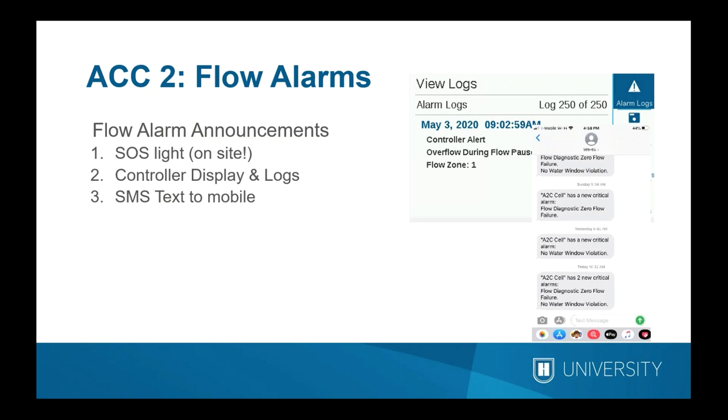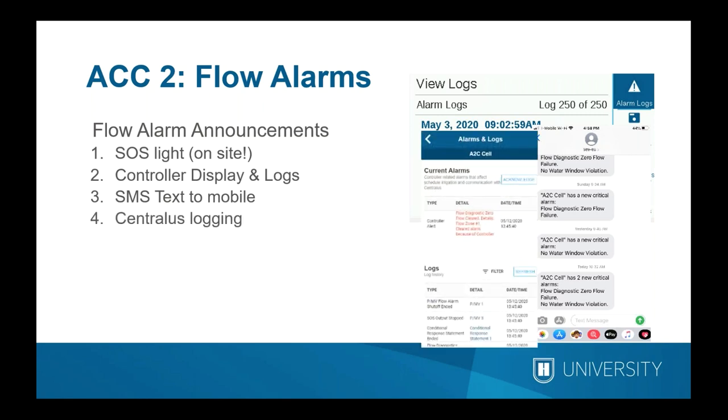The controller can also send an SMS text to your mobile device if it has been connected to the Centralus central control system. You can configure your mobile number to receive texts in near real time — for example, a message saying you have a flow diagnostic failure and a no-water window violation, both occurring within the last hour. If you log in with the Centralus central control software, you get all the detail contained in the controller. First thing in the morning, you'll have a text message on your phone; click into Centralus and it paints a complete picture of the problem so you can leave ready to deal with the situation.